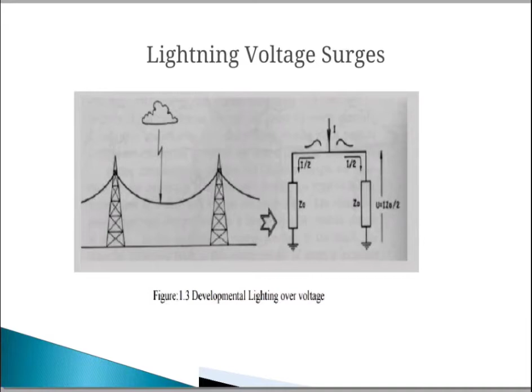The lightning current magnitude is rarely less than 10 kiloampere. For a typical overhead line surge impedance Z0 of 300 ohm, the lightning surge voltage will probably have a magnitude in excess of 1500 kV. Now we discuss what the effect of lightning is. The impedance of the lightning channel itself is much larger than half of Z0, and it is believed to range from 100 to 3000 ohm. The lightning voltage surge will have the same shape characteristic.